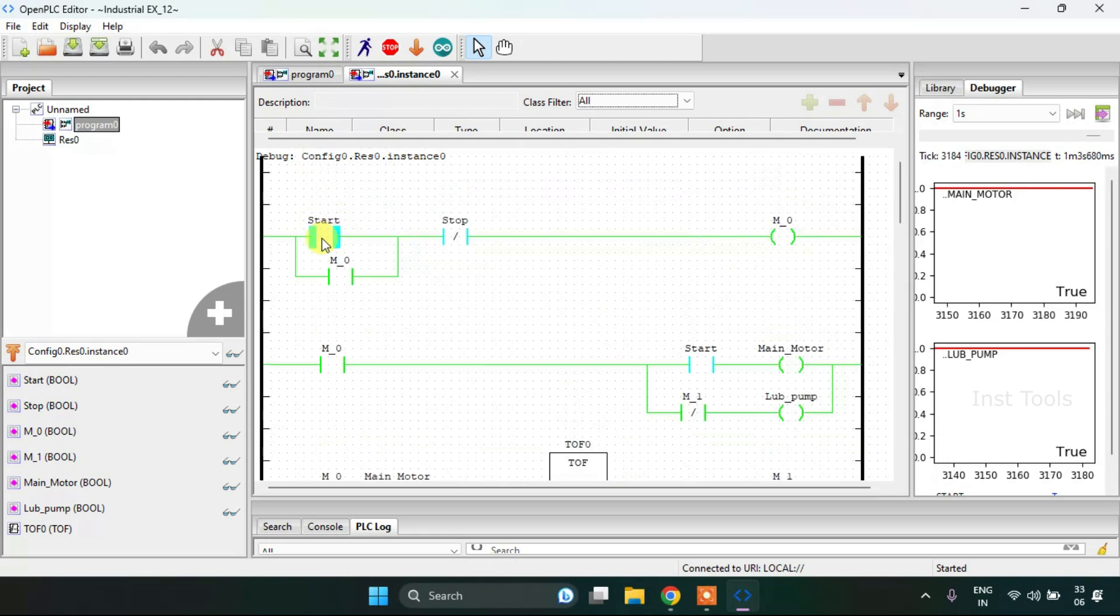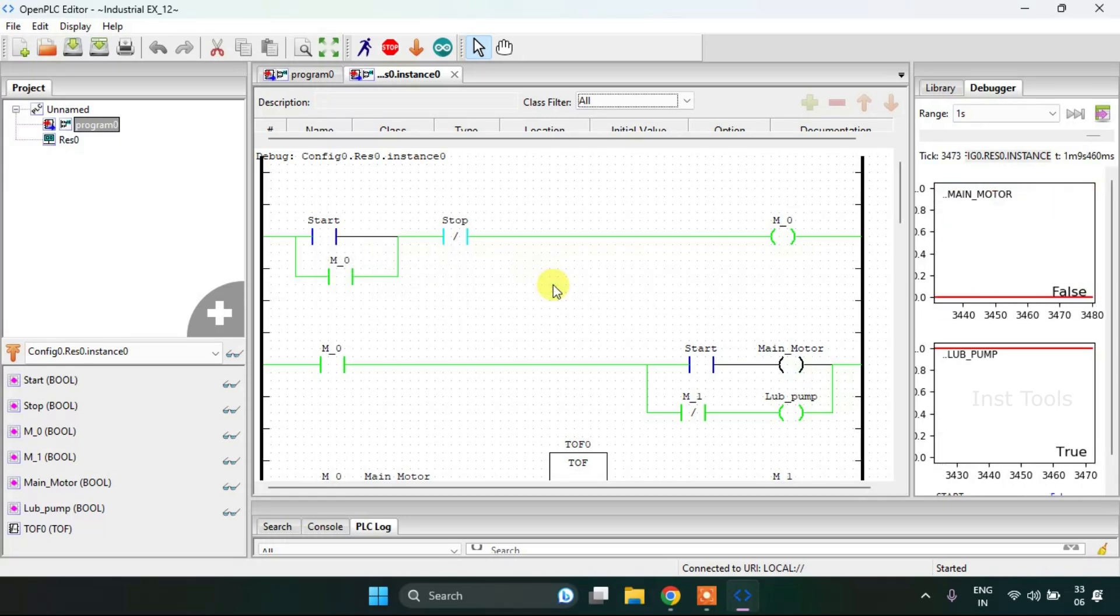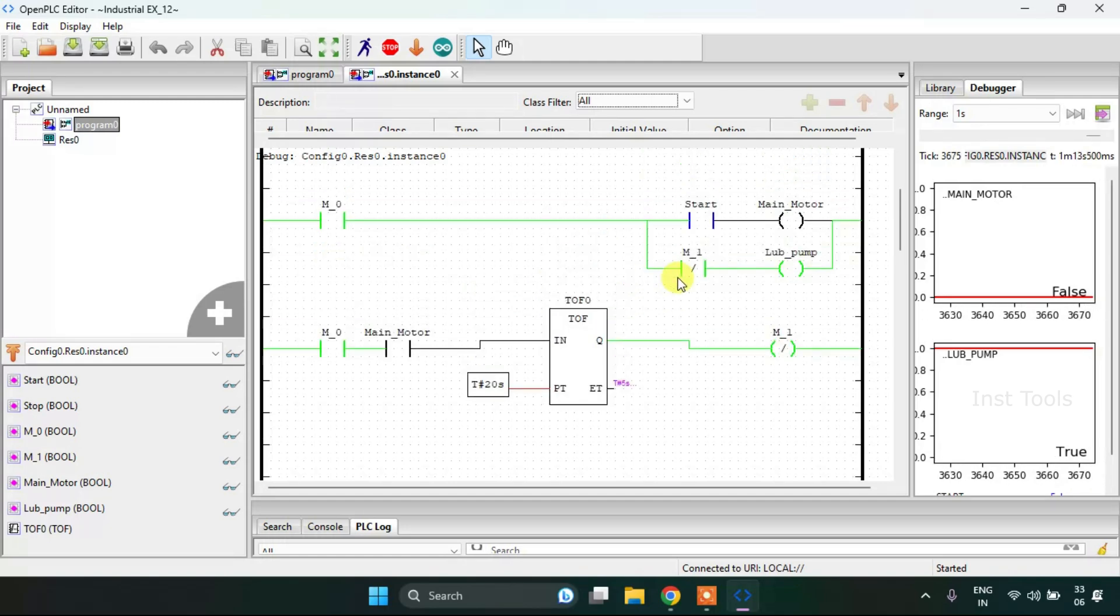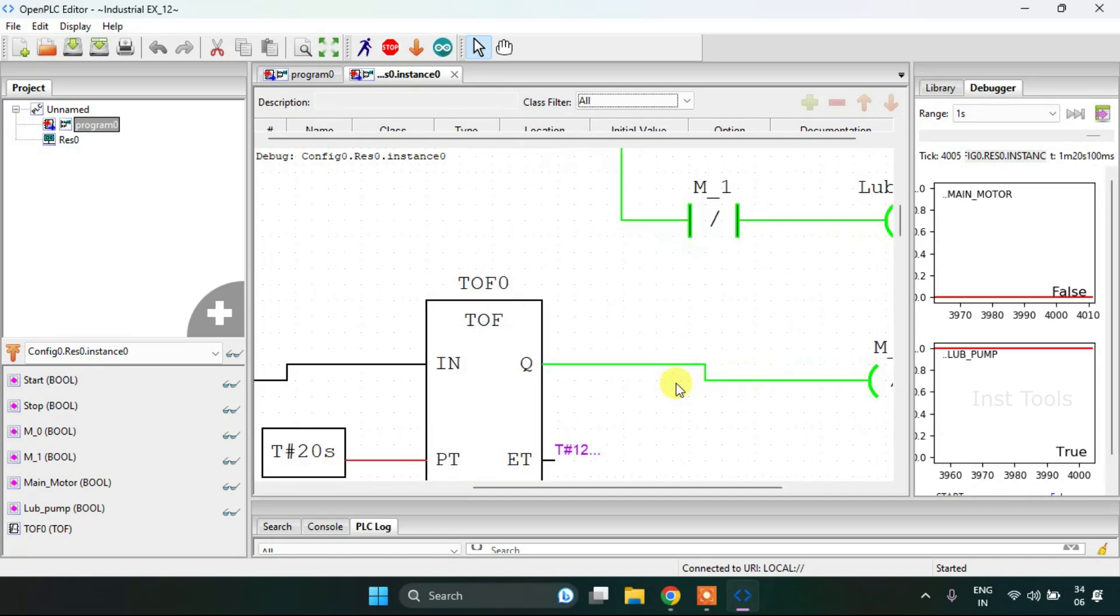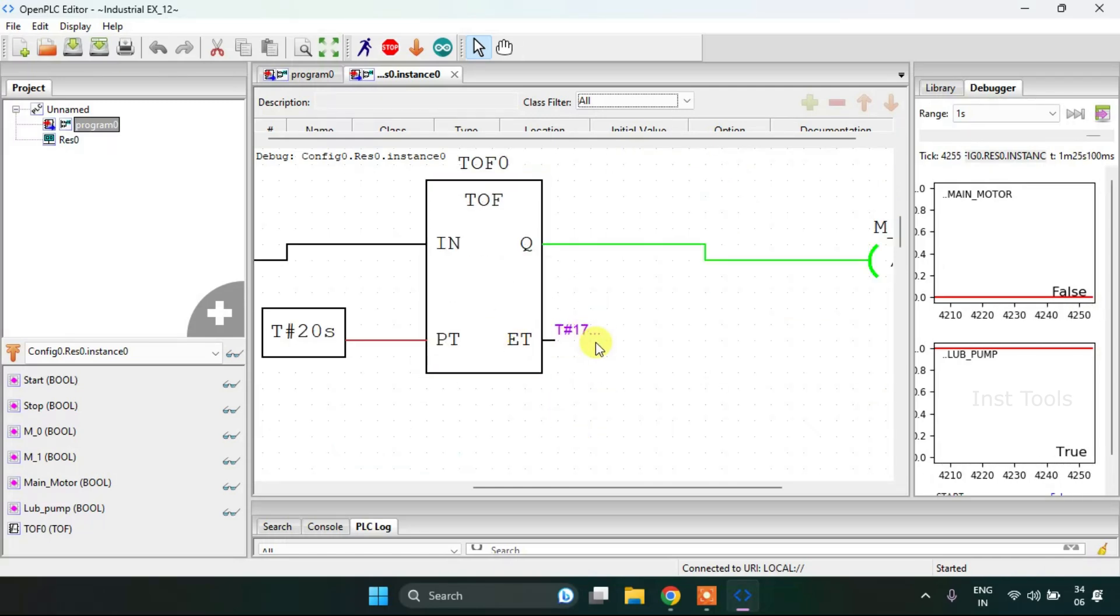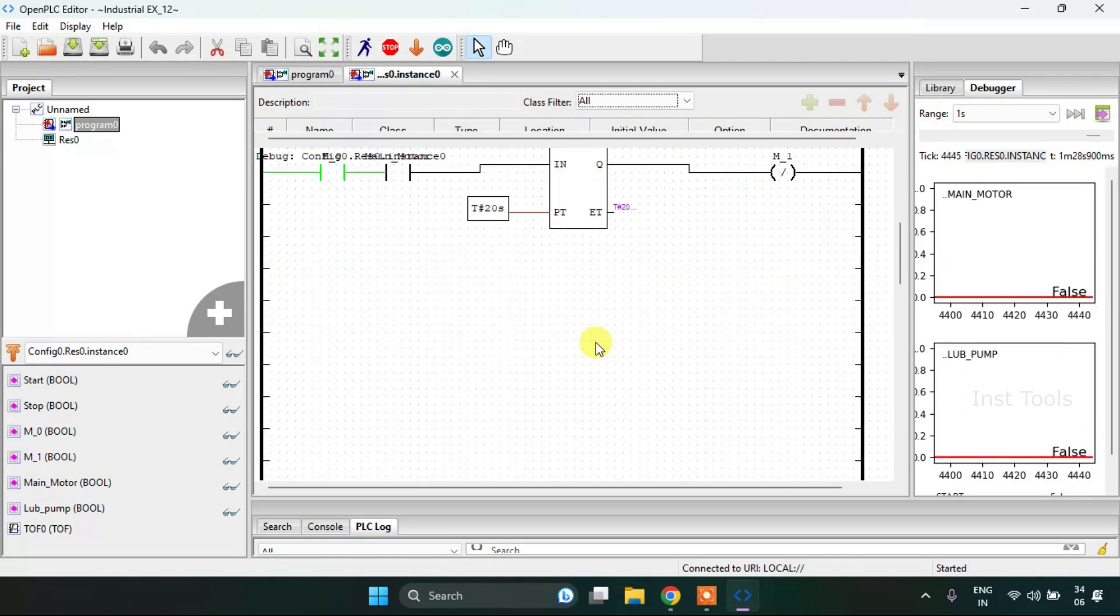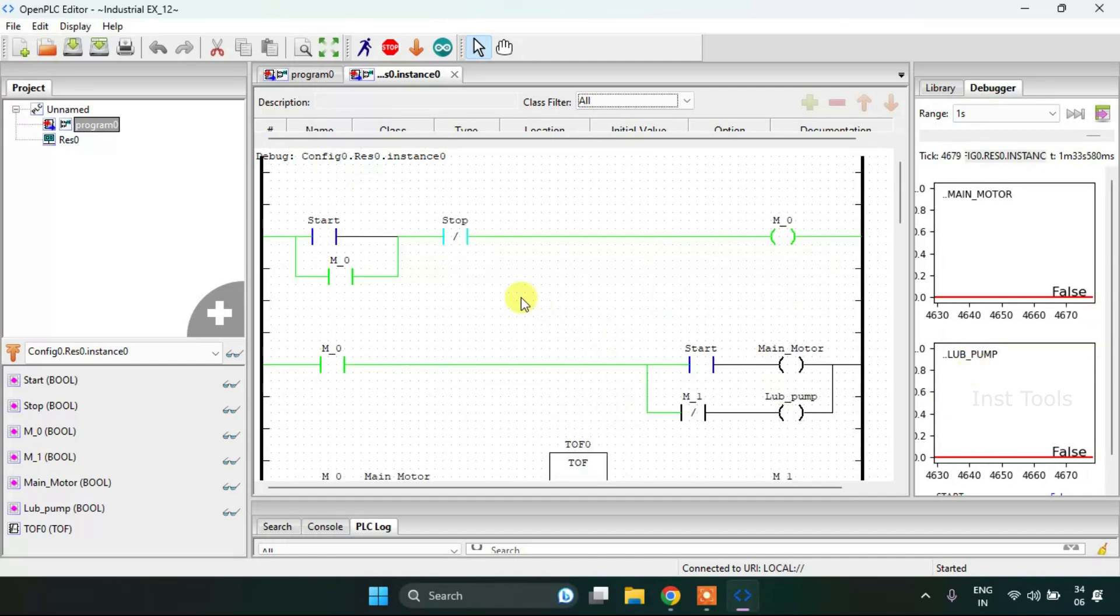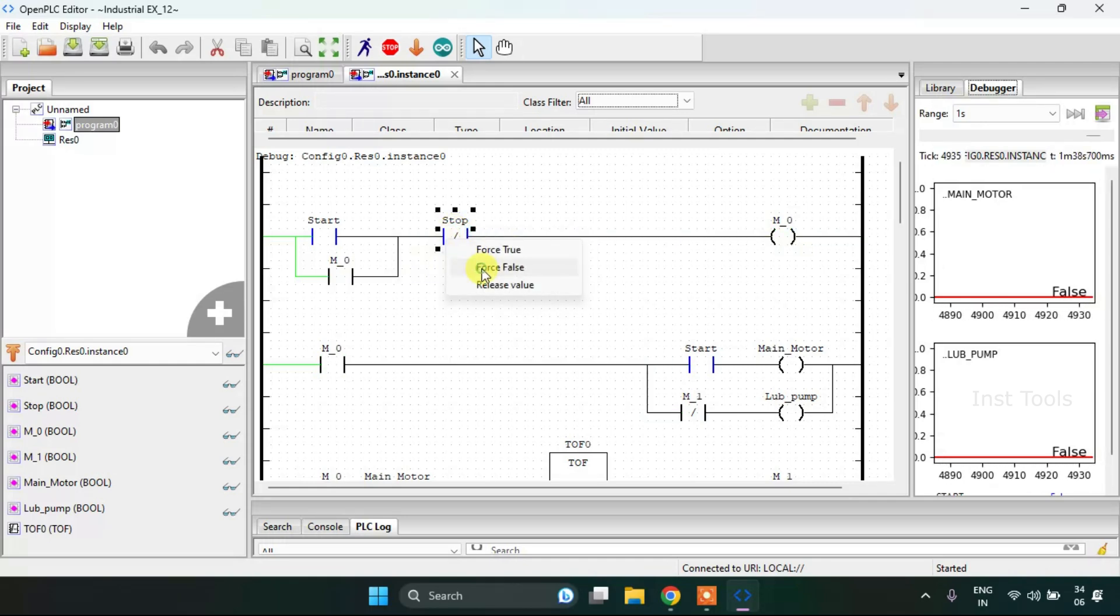After I stop the main motor, the lubricating pump should be true for 20 seconds. Now as you can see that the TOF is showing the elapsed time: 16, 17, 18, 19, and after 20 the pump will be off. By pressing stop you can shut down the whole thing.